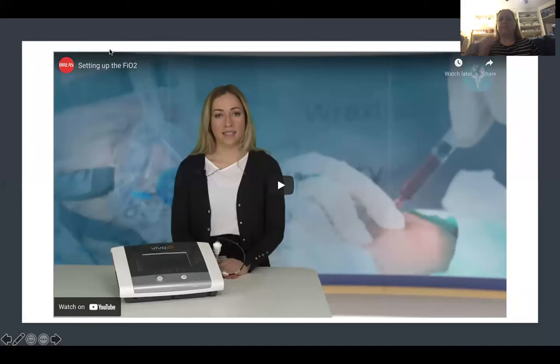Ventilators and BiPAPs, we don't usually calibrate the O2 sensors in those because they usually have pre-checks we do, and it will automatically calibrate the O2 sensor in that check. Here's a video with the Vivo 55. It's a little bit of a smaller ventilator, and it shows you how it works within the vent system.